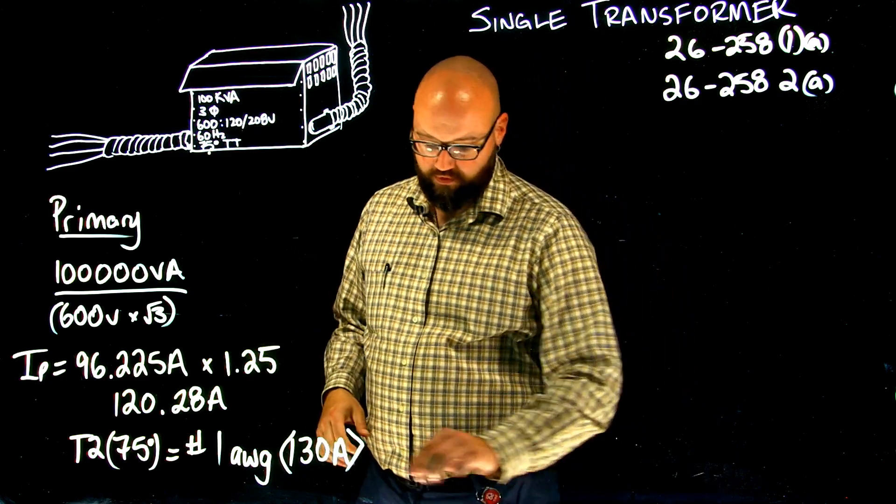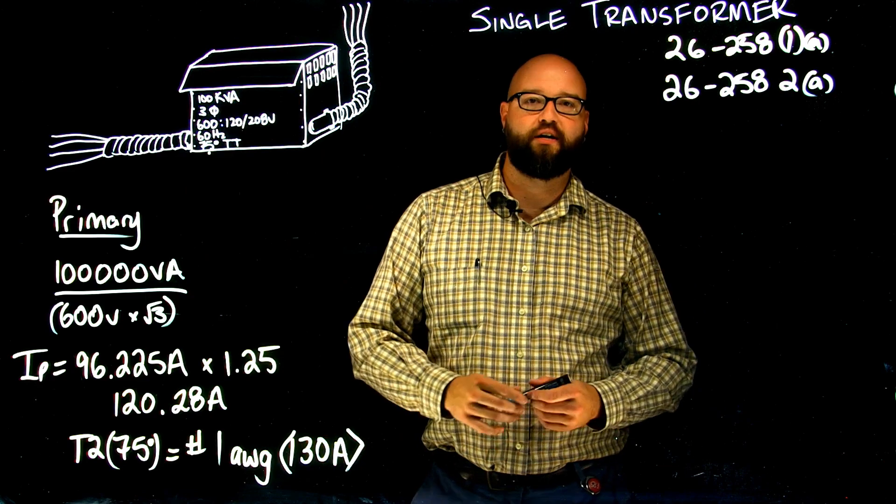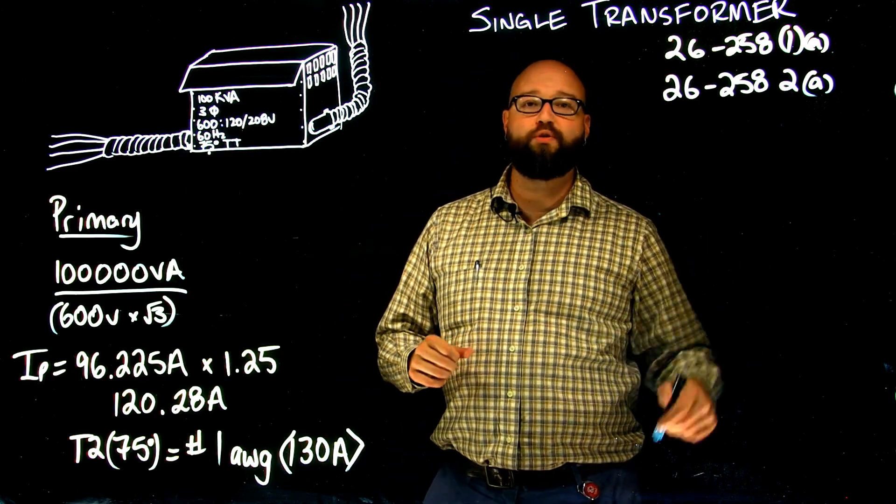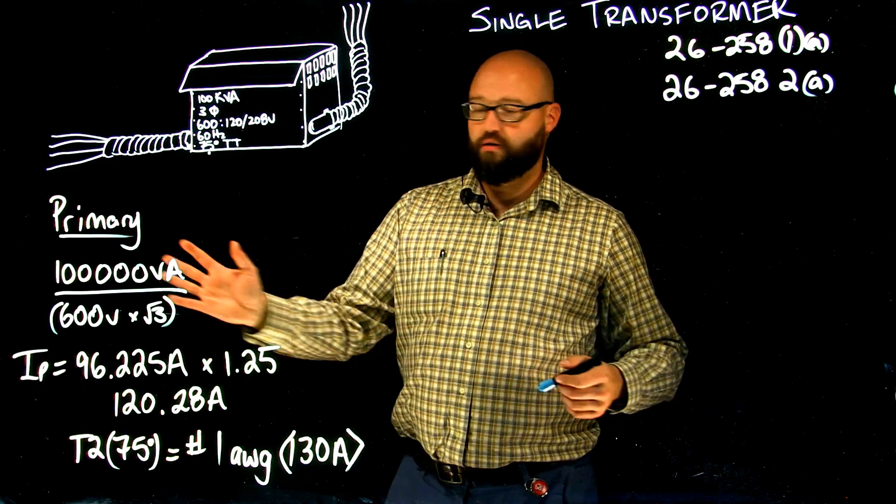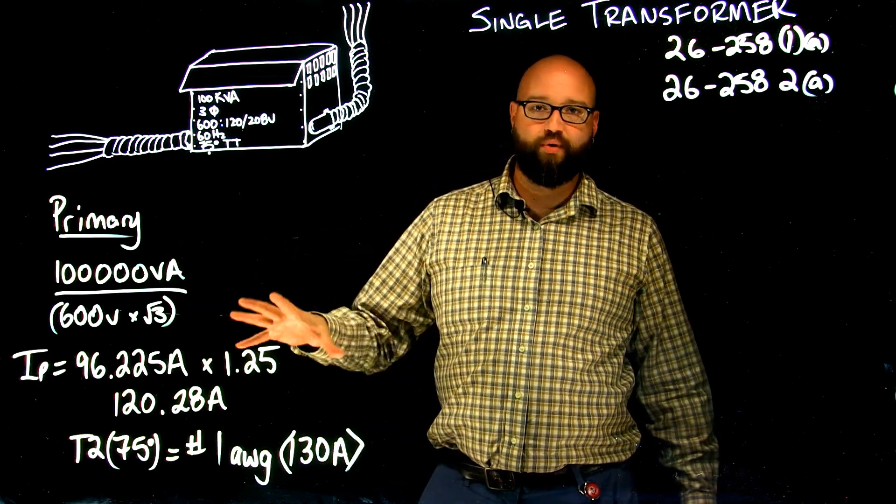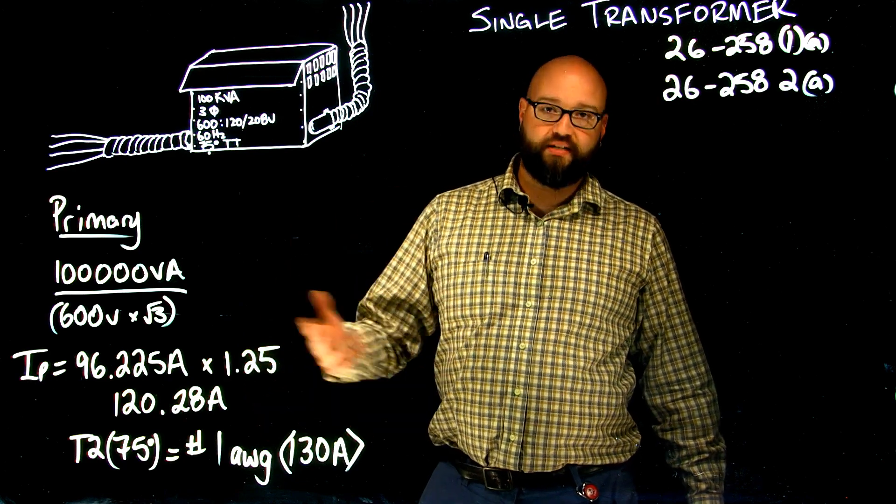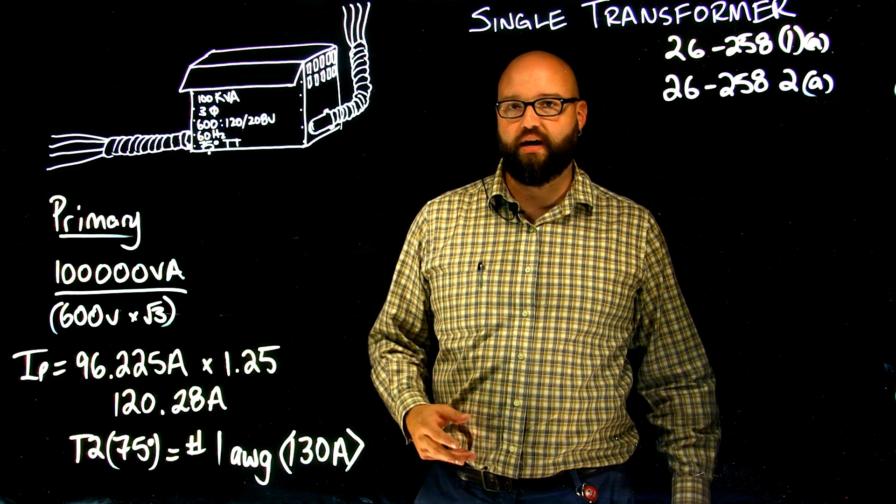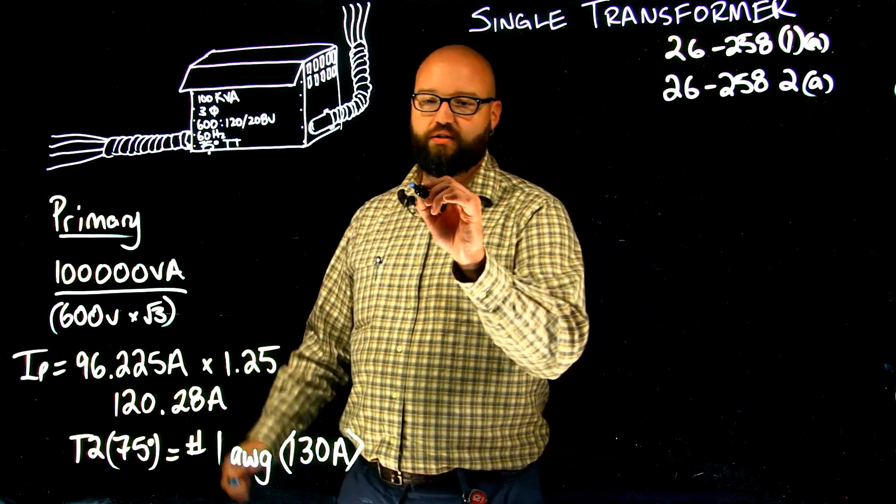So the next thing we're going to take a look at is calculating the secondary conductors of our single transformer. 26.258 subrule 2, item A, tells me exactly the same thing. We're going to take 125% of the rated secondary current, and that's going to be our minimum ampacity that we take to table 2 and select our conductor based off that. So, we'll do the calculation for our secondary.